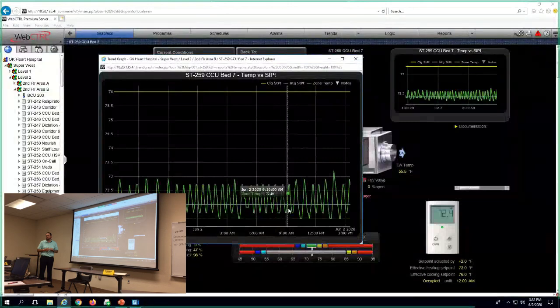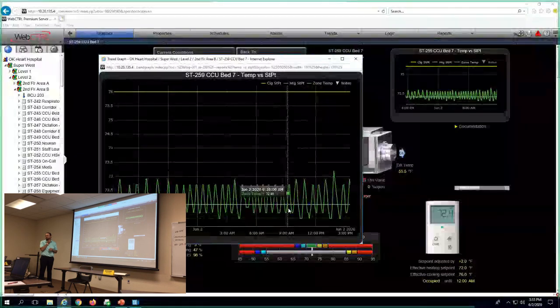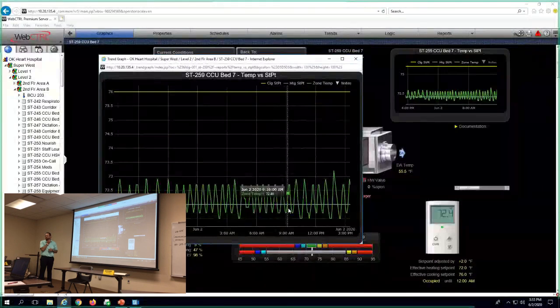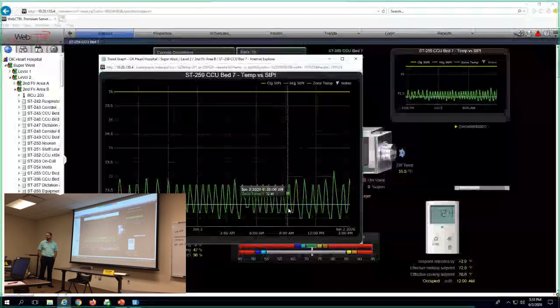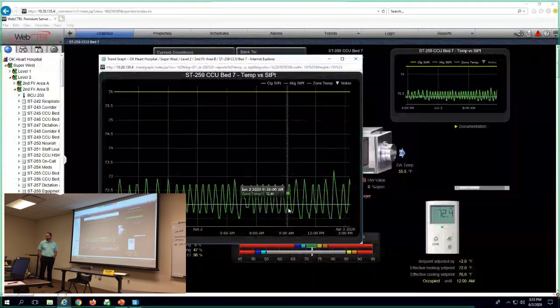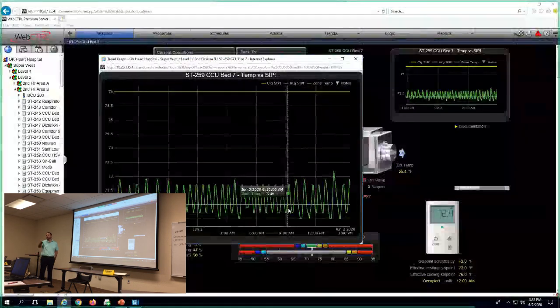So what you're saying is we need a tighter deadband and more plus and minus to be able to change the effective heating and cooling set points by potentially more than 4 degrees, plus or minus, to give them that comfort in those patient rooms to swing it. Yes, that's right. Set at 70 and 72, then 76 is going to be their top. It could potentially peak at 74 and stop. It would probably hover around 74. It's only going to warm it up to 74.